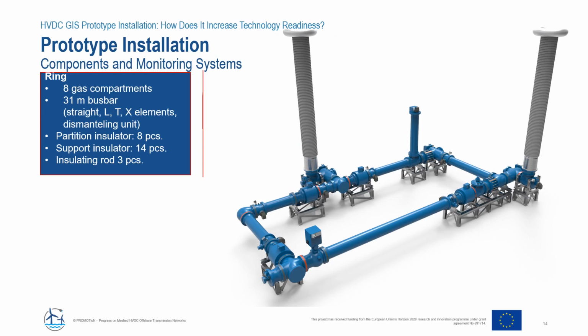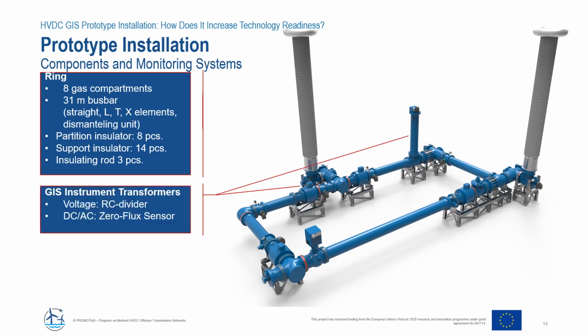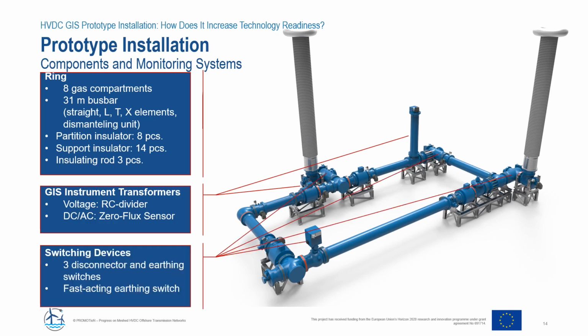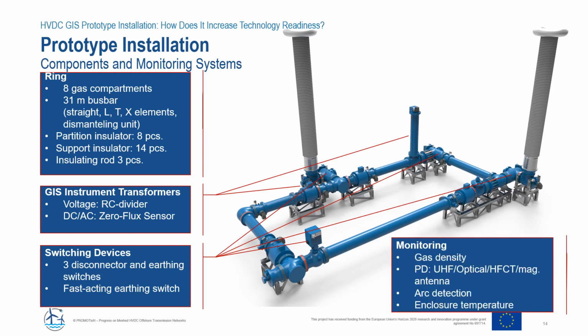The prototype installation consists of all major components needed for such an HVDC hub. We have different gas compartments, we have all kinds of modules, we have L, X, T-shaped modules. We have dismantling units. There are partition and support insulators, as well as disconnector insulating rods included as solid insulation. And we have DC capable instrument transformers, and we have the switching devices, the disconnector, earthing switches and the fast acting earthing switch included. We have also monitoring systems for gas density, PD, we have an established UHF system, as well as more experimental optical, high frequency current transformer and magnetic antenna systems. We have the arc detection and enclosure temperature monitoring systems.